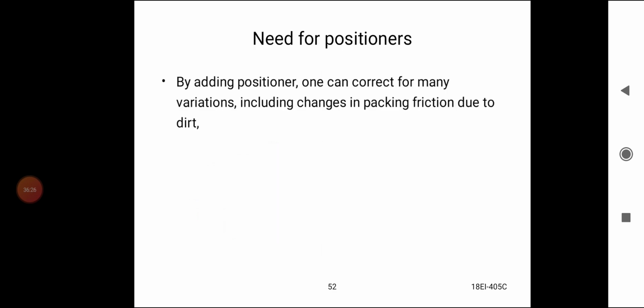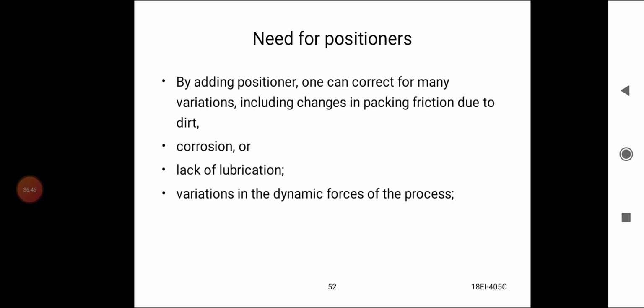Need for positioners. By adding a positioner, one can correct for many variations, including changes in packing friction due to dirt, corrosion, or lack of lubrication.